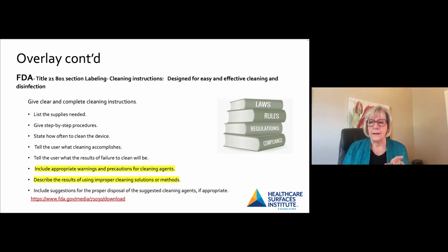I want to just quickly add something here, Barbara, because we've got some time. The Joint Commission has recently set a standard requirement, and they're enforcing it now. It's been there for a while. And that is that you follow the instructions for use and the guidelines from the manufacturers for cleaning and disinfection. And while this is great, what we have found are gaps.